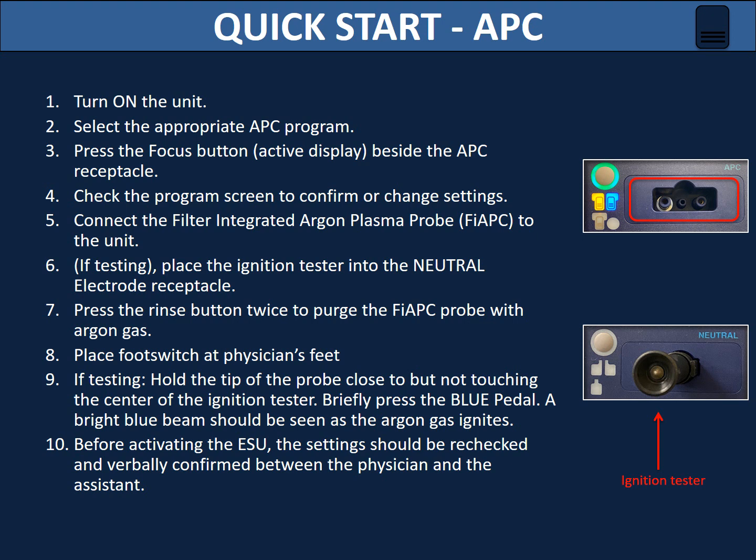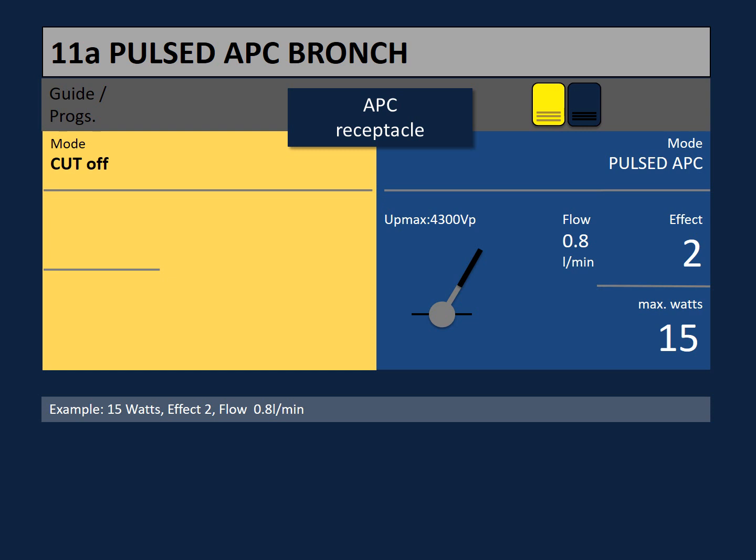In APC, the distal tip design of the probe determines the direction of argon gas flow, which can be axial, side fire, or circumferential. Place the pad on the patient and plug the return electrode into the neutral electrode receptacle. Before activating the ESU, the settings should be rechecked and verbally confirmed between the physician and the assistant. There is no ideal setting to be used during pulsed APC; it is always recommended to start by using the lowest possible setting that will achieve the desired surgical effect. It is worth mentioning that settings are usually higher when used for ablation. The APC probe must always remain in the clinician's field of vision and activated only when the tissue being treated is within the field of view.